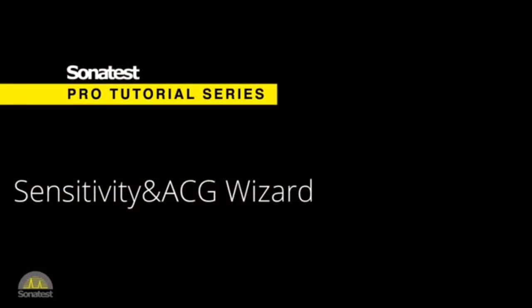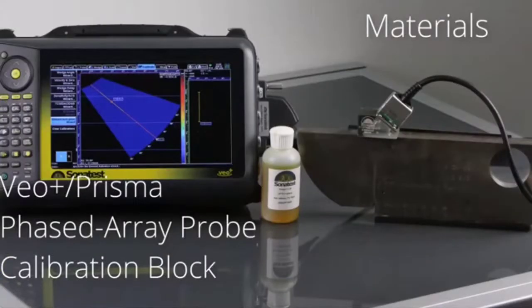This calibration should be realised after the velocity and the wedge delay calibration, but before the TCG calibration is performed. The purpose of this calibration is to level the signal response of the reflector for all the angles at the same reference level. To achieve this calibration, you are going to need a VEO Plus or Prisma instrument, a phased array probe and a reference block.